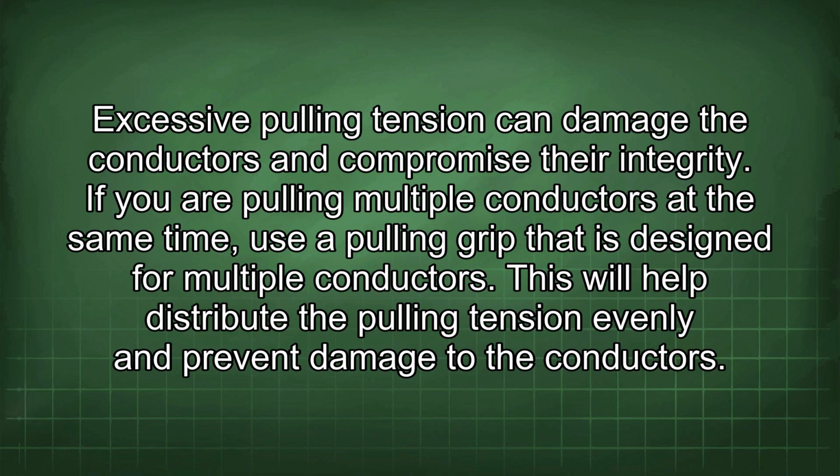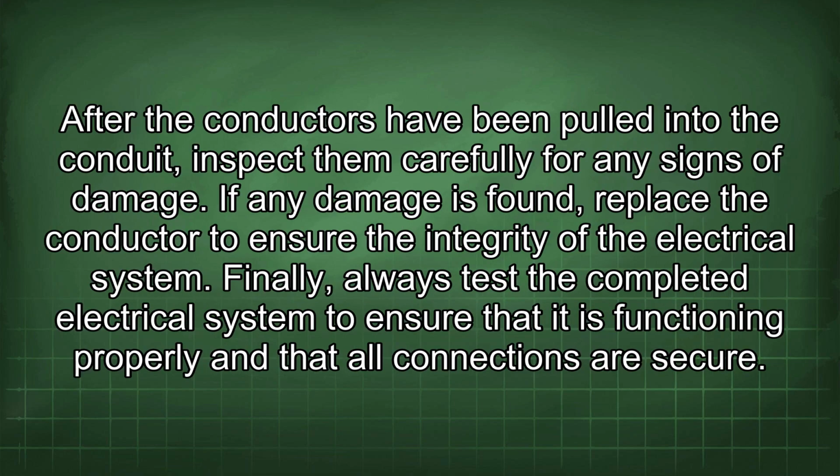If you are pulling multiple conductors at the same time, use a pulling grip that is designed for multiple conductors. This will help distribute the pulling tension evenly and prevent damage to the conductors. After the conductors have been pulled into the conduit, inspect them carefully for any signs of damage. If any damage is found, replace the conductor to ensure the integrity of the electrical system.